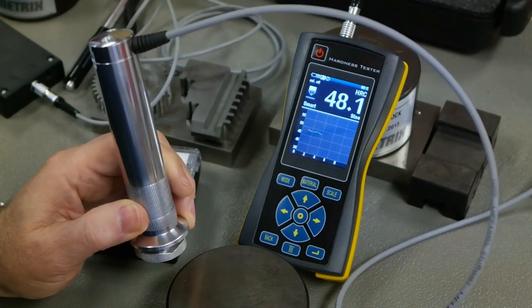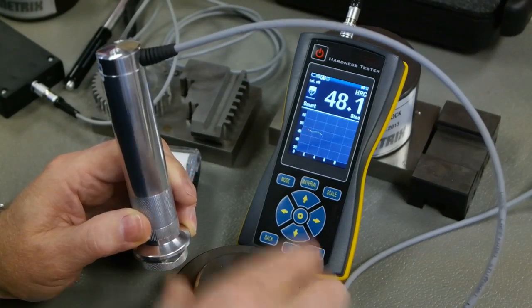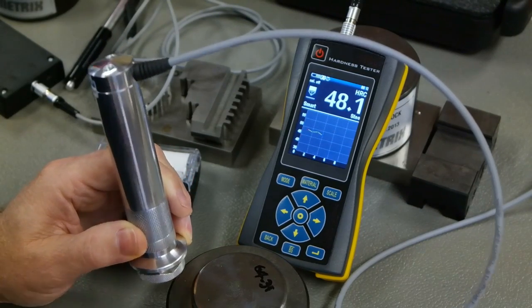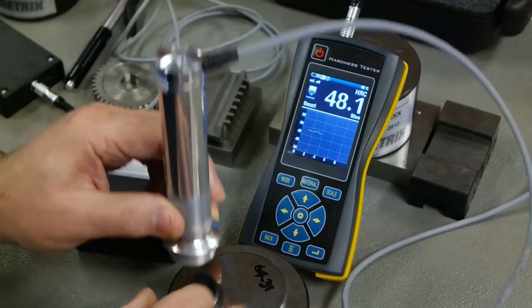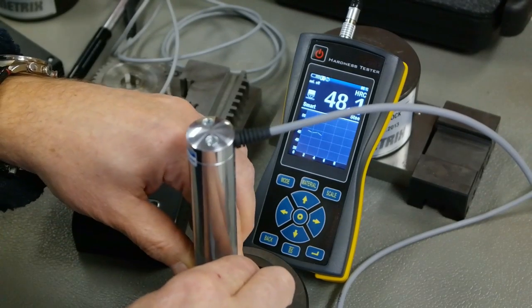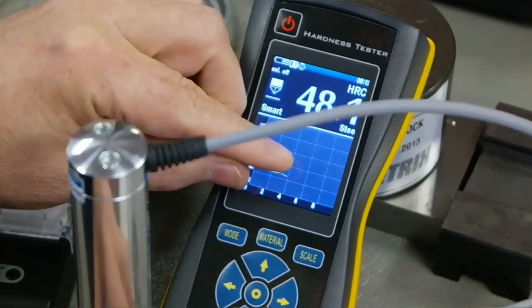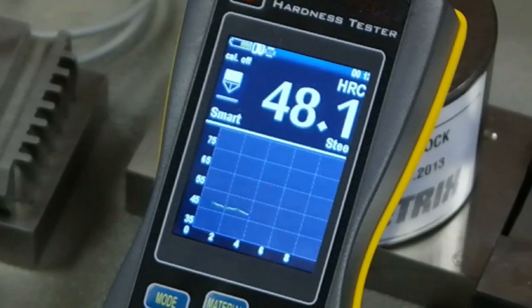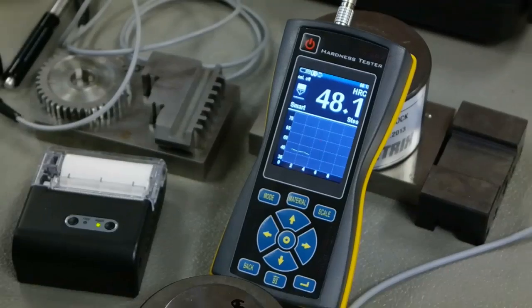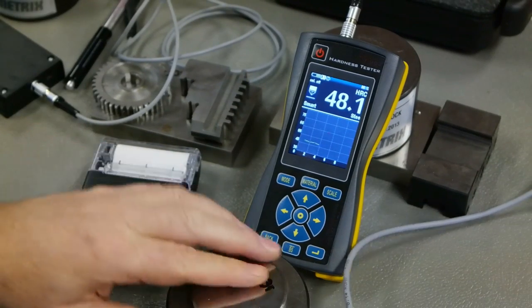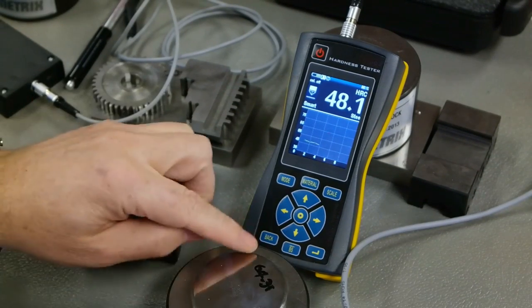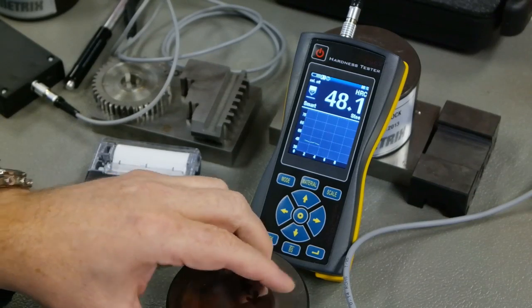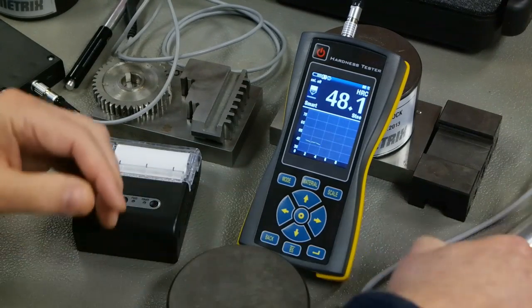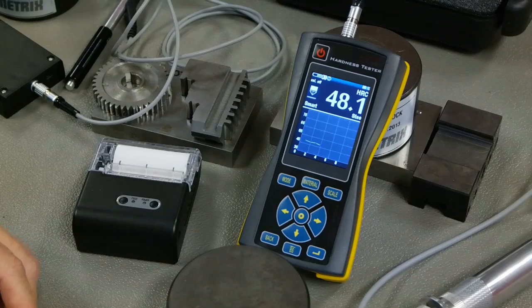Okay, now I'm going to jump to a material. Say this was a testing, and it was another part that I was testing, expected to be around 48, but I know it's 64. You can see here the little red dot has actually taken that test, but it's ignored it, it's tossed it out from my tolerance band. So it's a great way for new users, if they do a little bit of an erratic test, it'll automatically delete that rather than having to hit the backspace button. Great feature. Alright, so now we're going to look at the D-type probe.